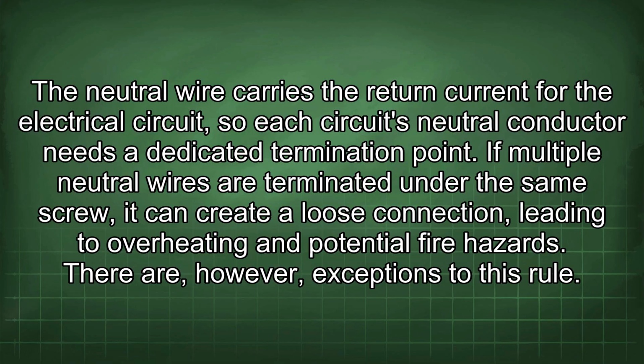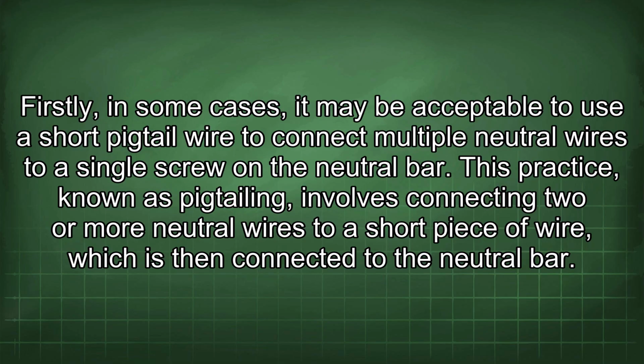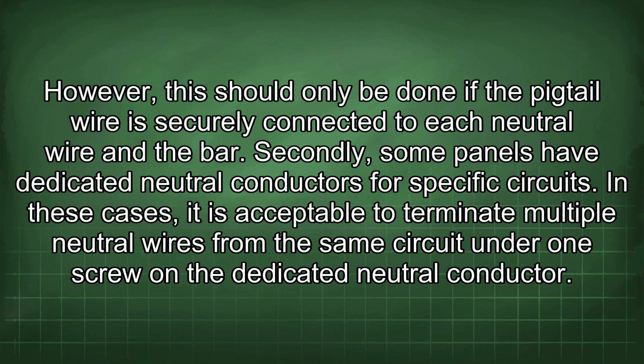There are, however, exceptions to this rule. Firstly, in some cases, it may be acceptable to use a short pigtail wire to connect multiple neutral wires to a single screw on the neutral bar. This practice, known as pigtailing, involves connecting two or more neutral wires to a short piece of wire, which is then connected to the neutral bar. However, this should only be done if the pigtail wire is securely connected to each neutral wire and the bar.